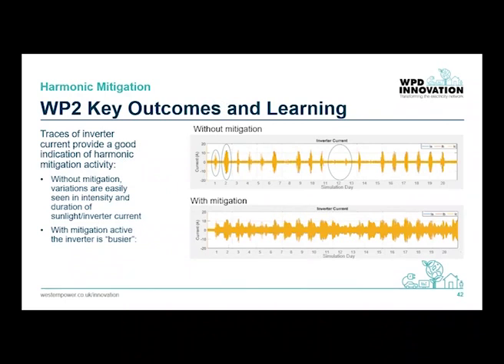If we now look at the same measurement, inverter current, but with the harmonic mitigation active, we see a considerably busier picture. We can see that the inverter is now active outside daytime periods. We also see that the controller is more active during some daytime periods when there is little sunlight. If we also look at the maximum inverter current, marked with the dashed lines, we see that current with harmonic mitigation is no higher than current without mitigation.